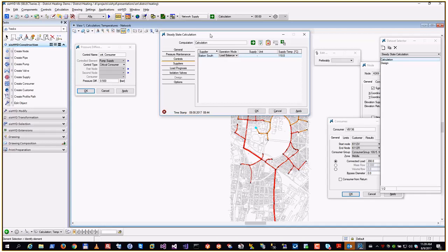If I have one station, I need one that can adjust to the requirements of flow. If we have multiple stations, we can operate one with a constant mass flow or with a constant heat, so that it feeds in a fraction of the required demand. But in a single case, for a single supply station, it's always load balance mode.